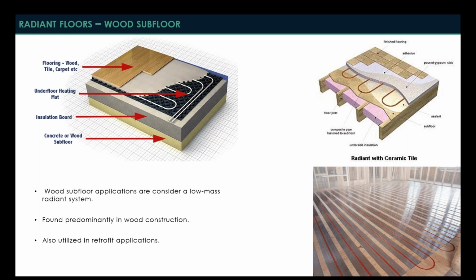Another type of radiant floor is a wood subfloor system. Now, it's not too dissimilar from the concrete system in that you're running PEX tubing beneath some sort of substrate to transfer energy into the space. However, this would be considered a low mass radiant system because you're not getting the benefit of the thermal mass of that concrete. So the system traditionally is put into what I would call a wood subfloor track. The bottom right image shows the radiant tubing installed in preformed channels in a wood subfloor. And then there are aluminum panels that are connected to the tubing. And really that's just to increase the heat transfer from the tubing to the floor system. Oftentimes you will find these types of applications in predominantly wood construction, or also in retrofit applications where pouring a new concrete slab simply isn't possible.